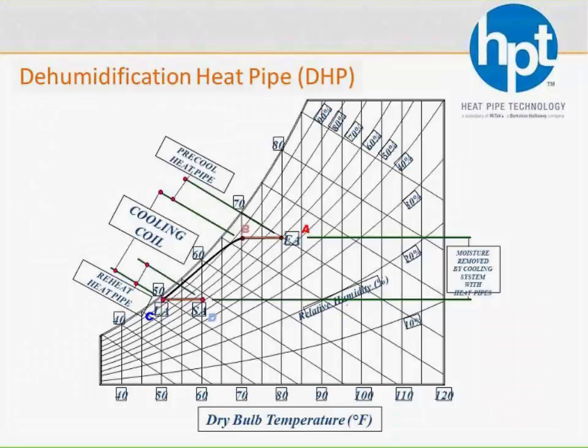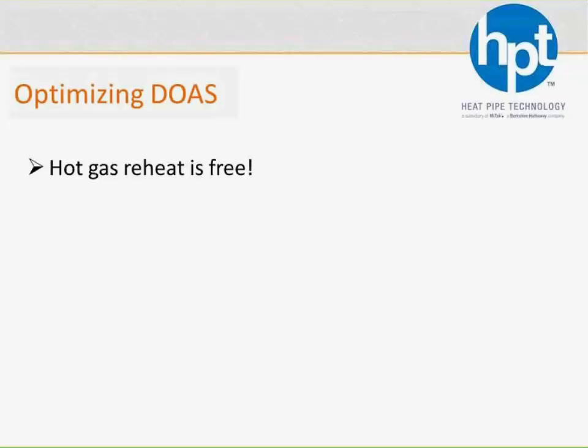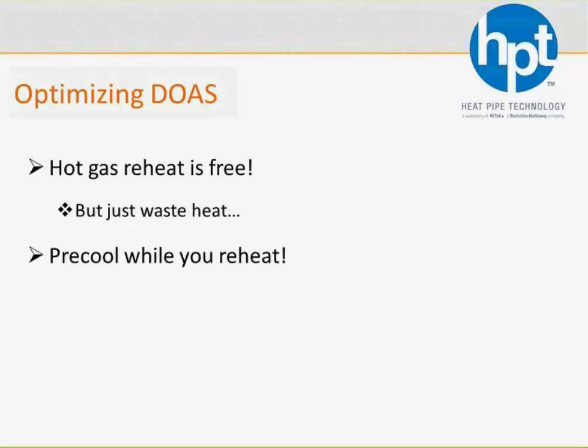So for dedicated outside air systems, if it's DX, then of course that reheat is free anyway. You can use hot gas reheat, get you some free reheat, and everybody's happy. That's a big chunk of savings right there. But the downside is that it's just waste heat. I mean, I don't want to downplay free heat because that's awesome, but it is just waste heat. When you compare it to the wraparound heat pipe, you're not just getting free reheat, but you're getting free cooling as well.